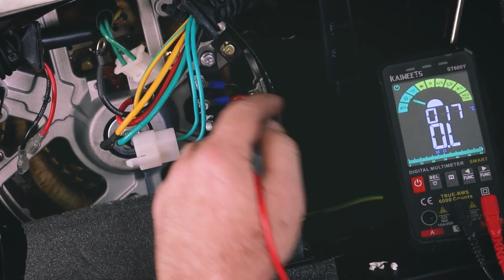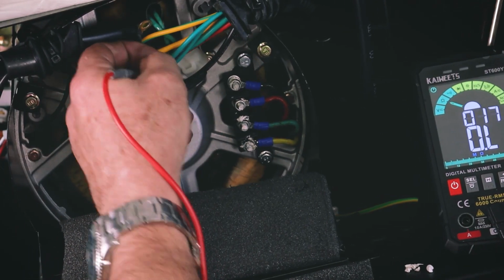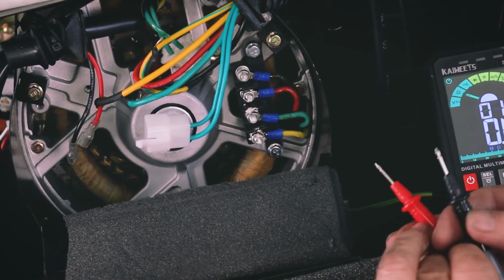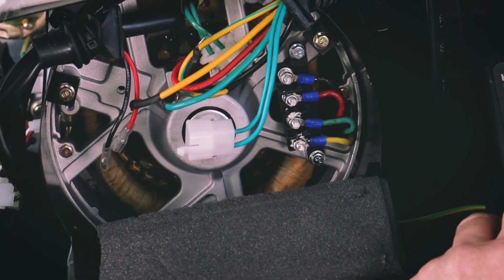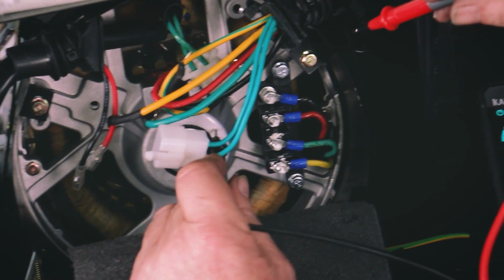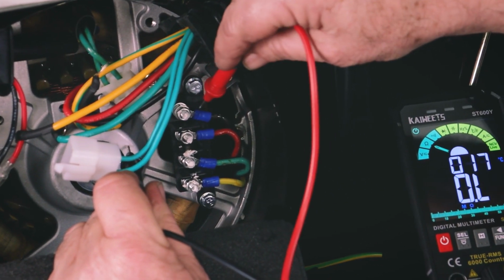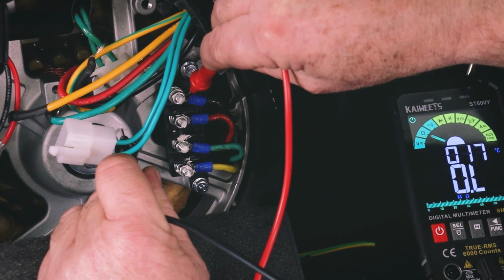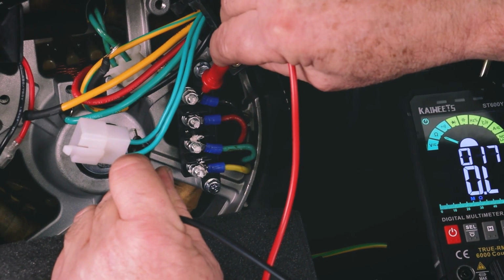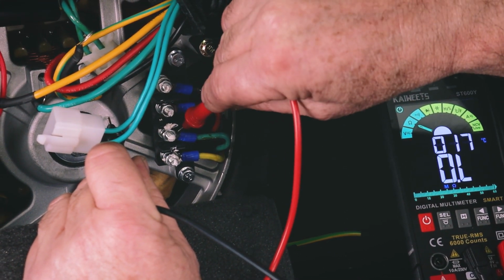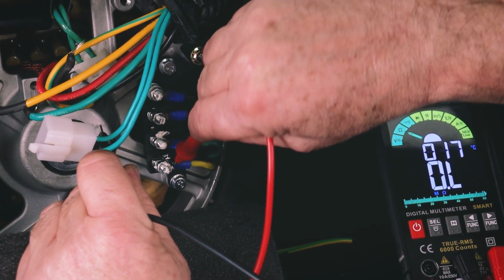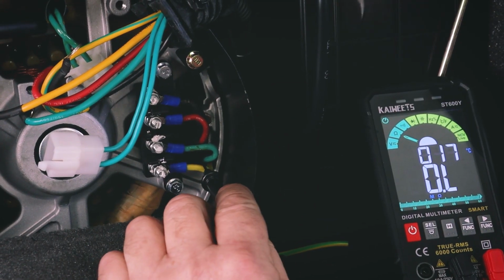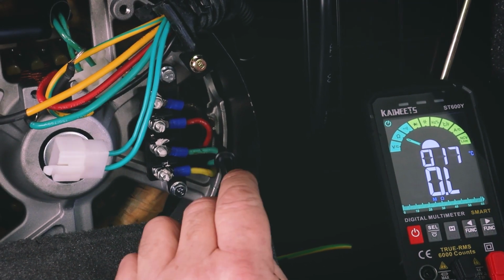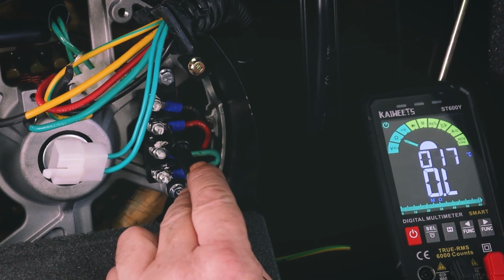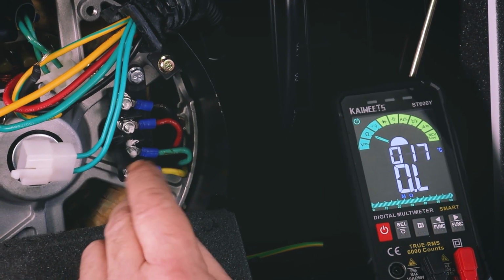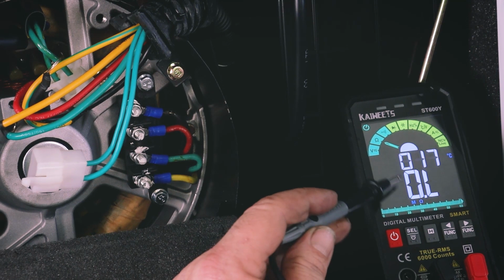So the next check is making sure that none of these windings are going to ground. So how we do that is I'm on resistance. Again, let's just see. So I should be over limit when I touch this, complete insulation. Touch any one of these wires, and as you can see on my meter, over limit, absolutely nothing. So that's a good one. Okay.